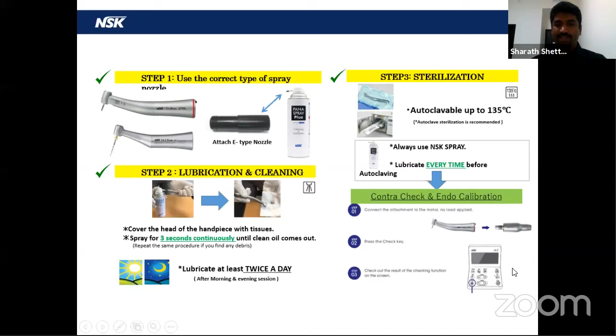In case you see some blackish particles, repeat this procedure until you get clean oil coming out. Have a practice of lubricating at least 2 times a day. If you lubricate after every operation, well and good. That's a very good practice. But in case you do not have time or for some other reason, no issues. At least 2 times a day, you have to lubricate the handpiece, and every time before autoclaving. Okay. So this is all the basic information about lubrication.